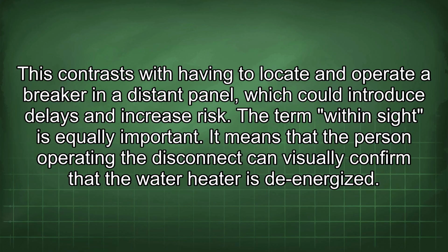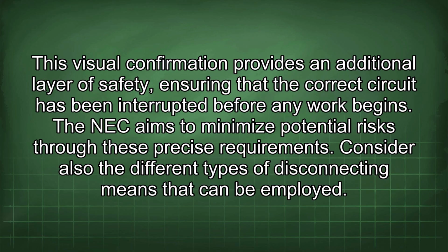It means that the person operating the disconnect can visually confirm that the water heater is de-energized. This visual confirmation provides an additional layer of safety, ensuring that the correct circuit has been interrupted before any work begins. The NEC aims to minimize potential risks through these precise requirements. Consider also the different types of disconnecting means that can be employed.